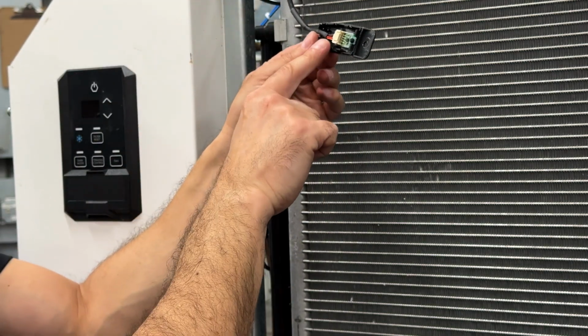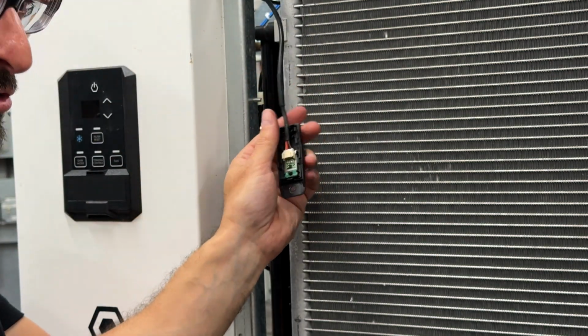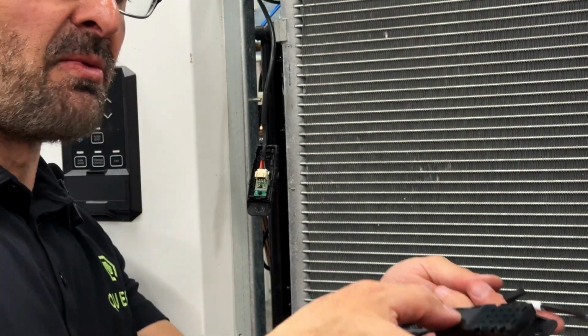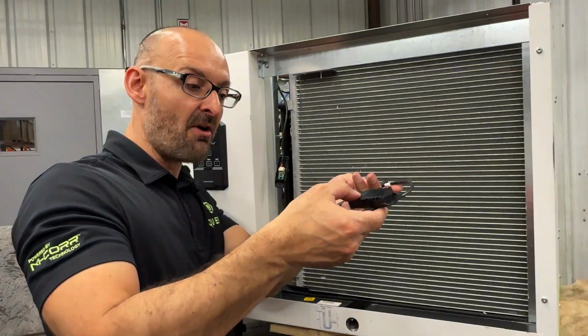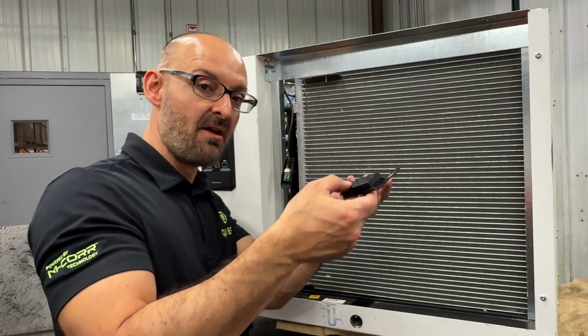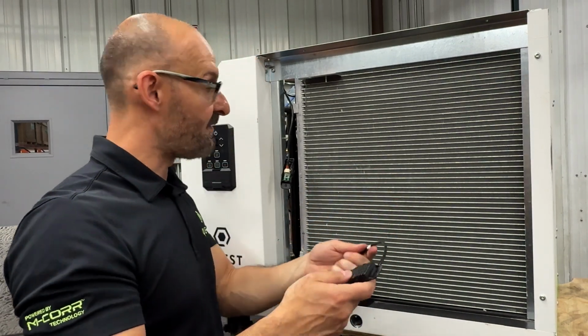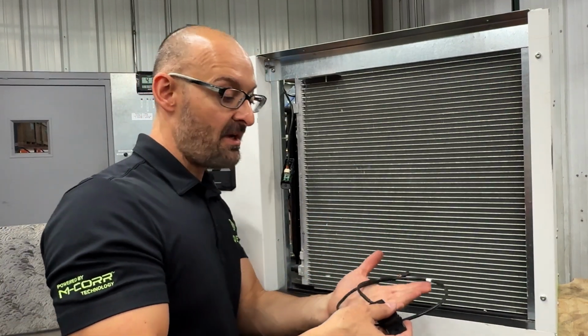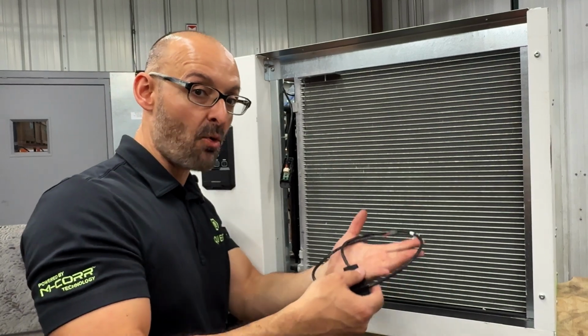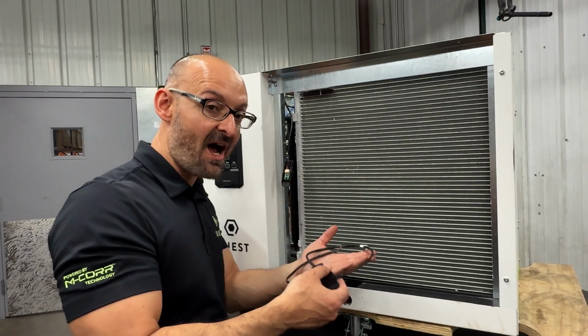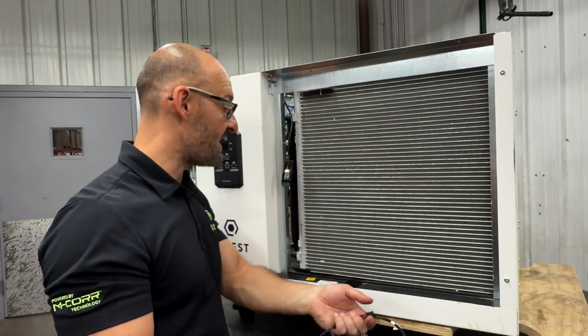Instead of replacing the entire part, we're just going to replace the sensor. Usually what happens is Tech Service will send you the whole part, wire and all, sensor wire and all, for a quick replacement. But instead of having to open up your unit and get to the power board and replace the entire part, we're just going to replace the head of the sensor.